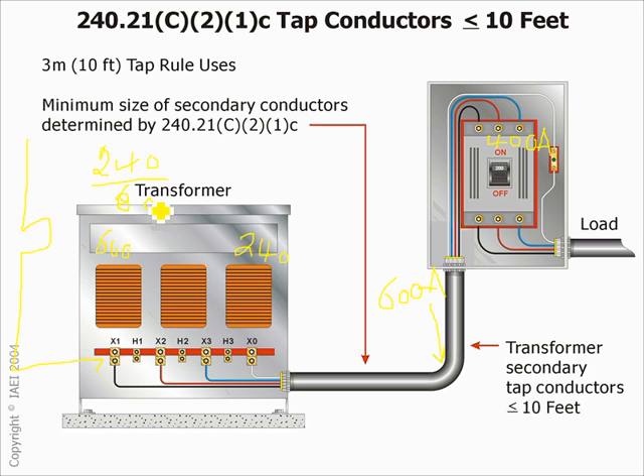600 multiplied by. Now, what would you multiply by here? Well, 600 kcm though. Multiplied by, well, typically the ampacity of the conductor. The ampacity of the conductor is going to be more than 400, right? What's the ampacity of 600? 400 something? How much? 420. So you multiply this by the ampacity of the conductor, which is 420, because that's what you're protecting, right? And what would that give you, William? How much? 168?